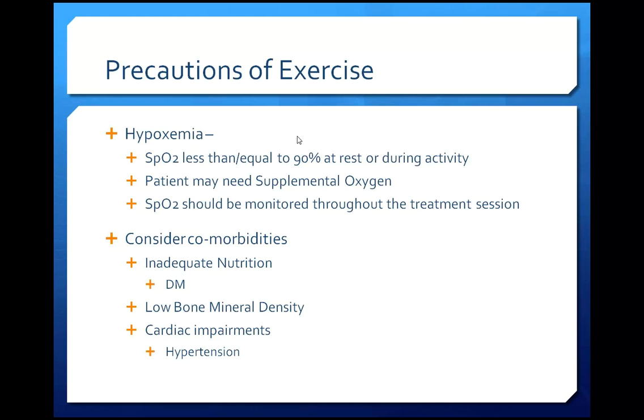I'm trying to make sure I use the same finger to get a consistent reading. It's going to be plus or minus 2% for most of the standard errors of the pulse oximeter. Even the small, cheap ones are about 2%. So that's something to watch.